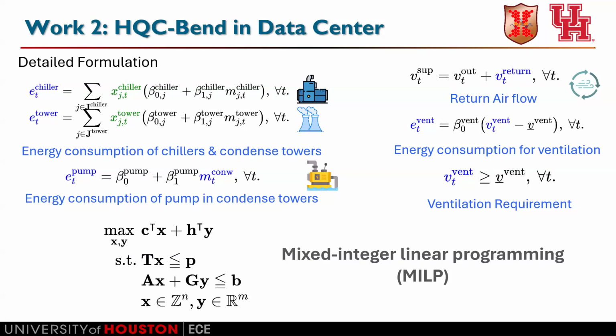Once we calculate how much heat we need to extract, we can compute the energy consumption of the chiller and condensed tower, as well as the pumps in the condensed towers, where beta represents the coefficients. Similarly, we compute the energy consumption for ventilation and return airflow, along with the ventilation requirements. Beta again represents coefficients; continuous variables are marked in this color, and binary variables in this color. So our problem can be generalized as a mixed integer linear program, MILP.